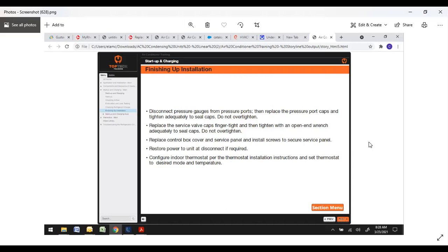We used to chase guys after winter, or even tune-ups. You guys will leave disconnects off, things like that. If they do that, they haven't obviously done a good job checking to make sure it was running when they left. So always cycle them off, cycle them back up. That way you can verify at the time you're leaving, everything is functional as it should be.